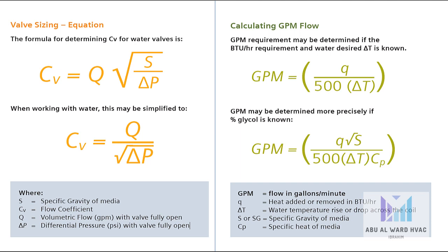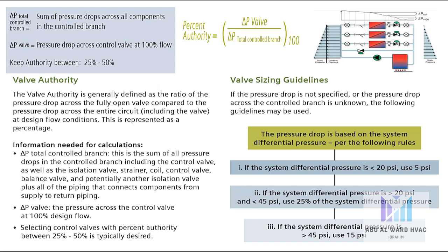We can also calculate GPM for water as: GPM equals Q divided by 500 multiplied by ΔT. If we have another material such as glycol, GPM is calculated as Q multiplied by the square root of S, divided by 500 times ΔT times Cp.